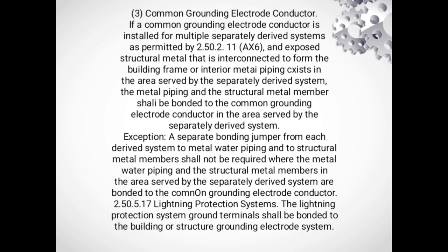Common grounding electrode conductor. If a common grounding electrode conductor is installed for multiple separately derived systems as per 2.50.2.11, and exposed structural metal that is interconnected to form the building frame or interior metal piping exists in the area served by the separately derived system, the metal piping and the structural metal member shall be bonded to the common grounding electrode conductor in the area served by the separately derived system. Exception A. A separate bonding jumper from each derived system to metal water piping and structural metal member shall not be required where the metal water piping and the structural metal members in the area served by the separately derived system are bonded to the common grounding electrode conductor.